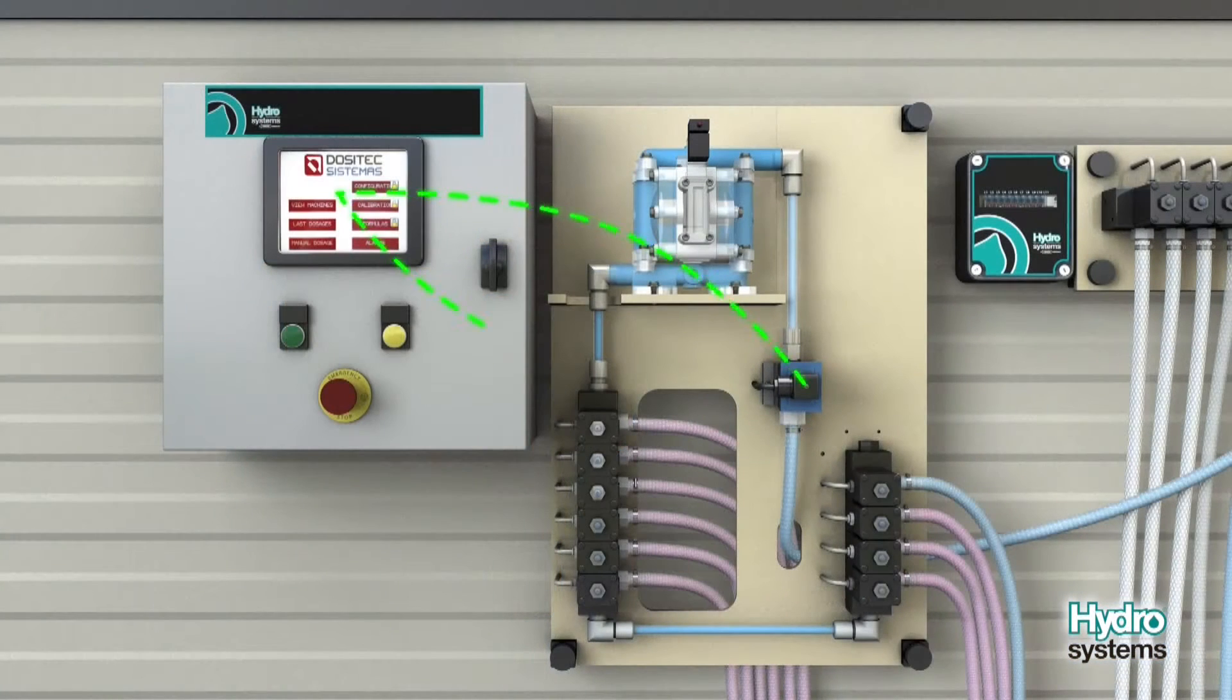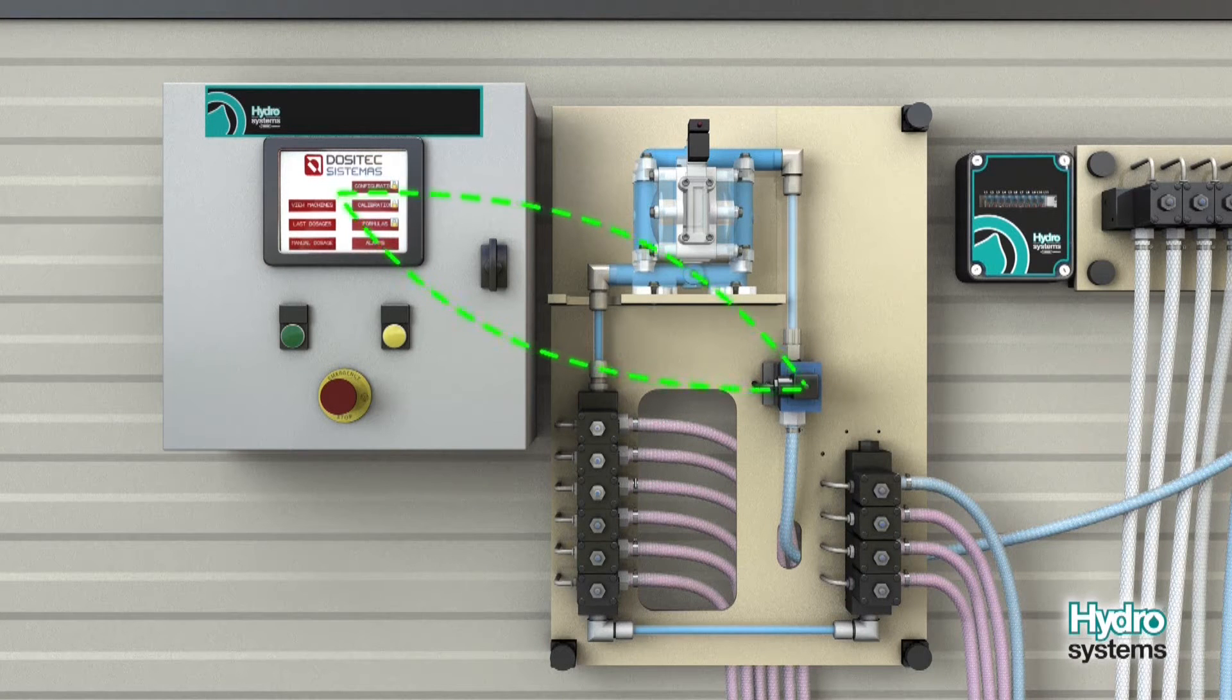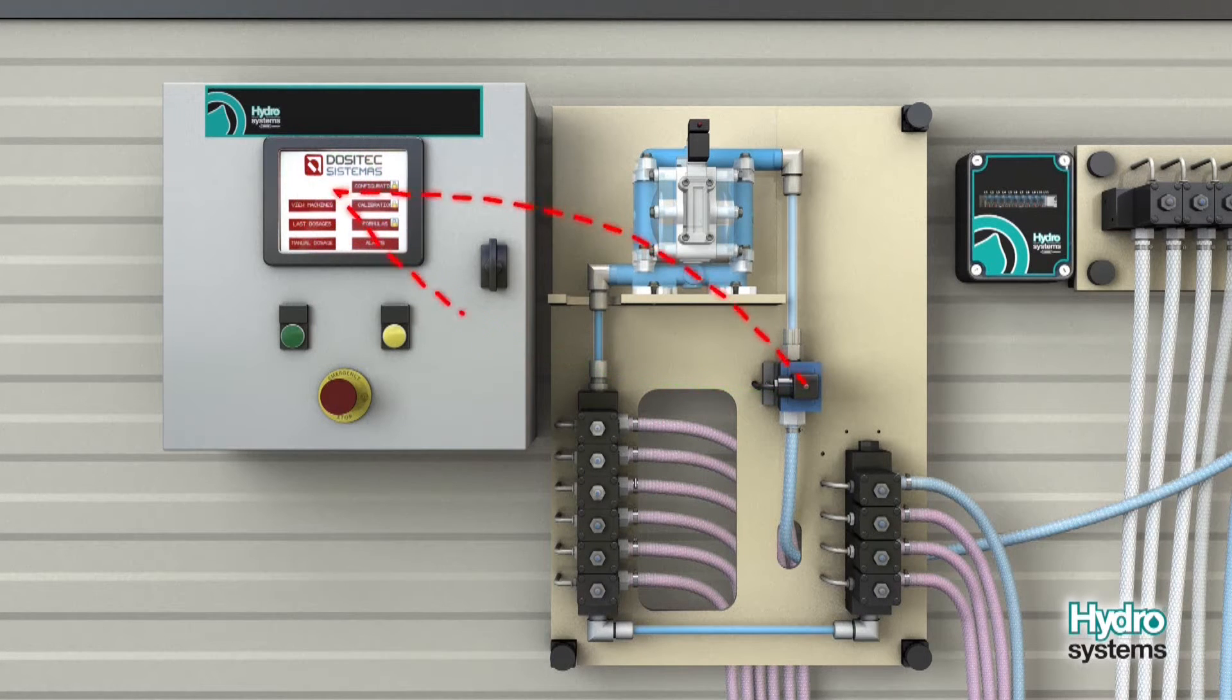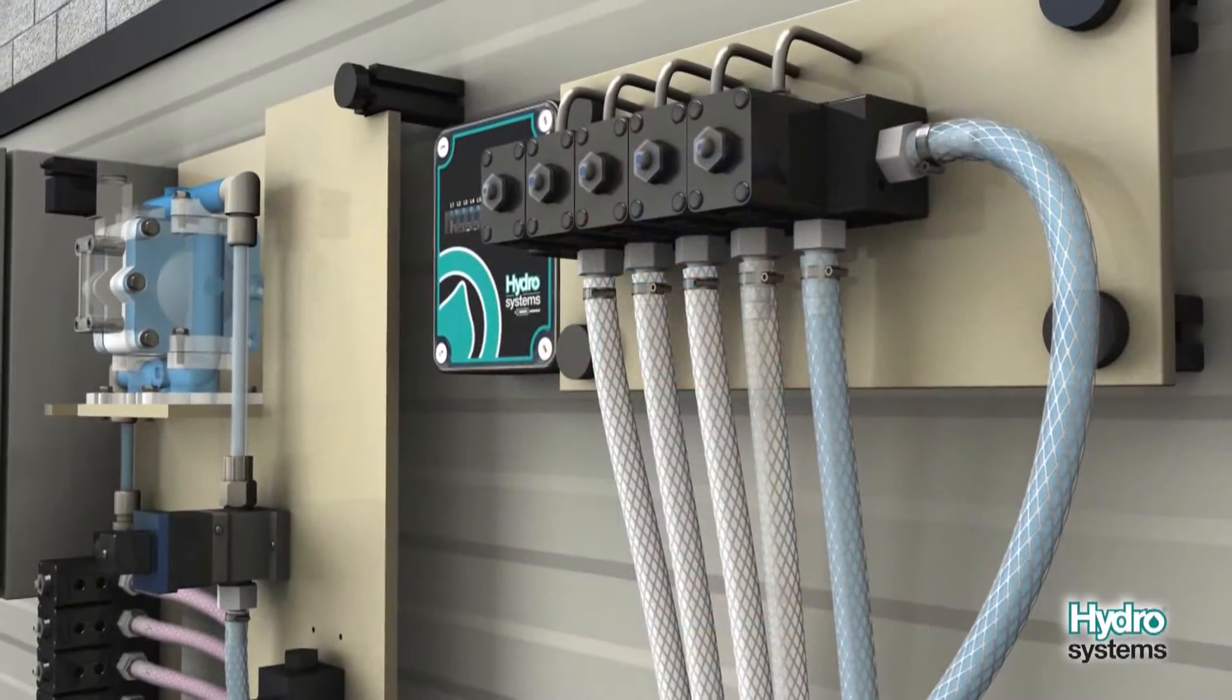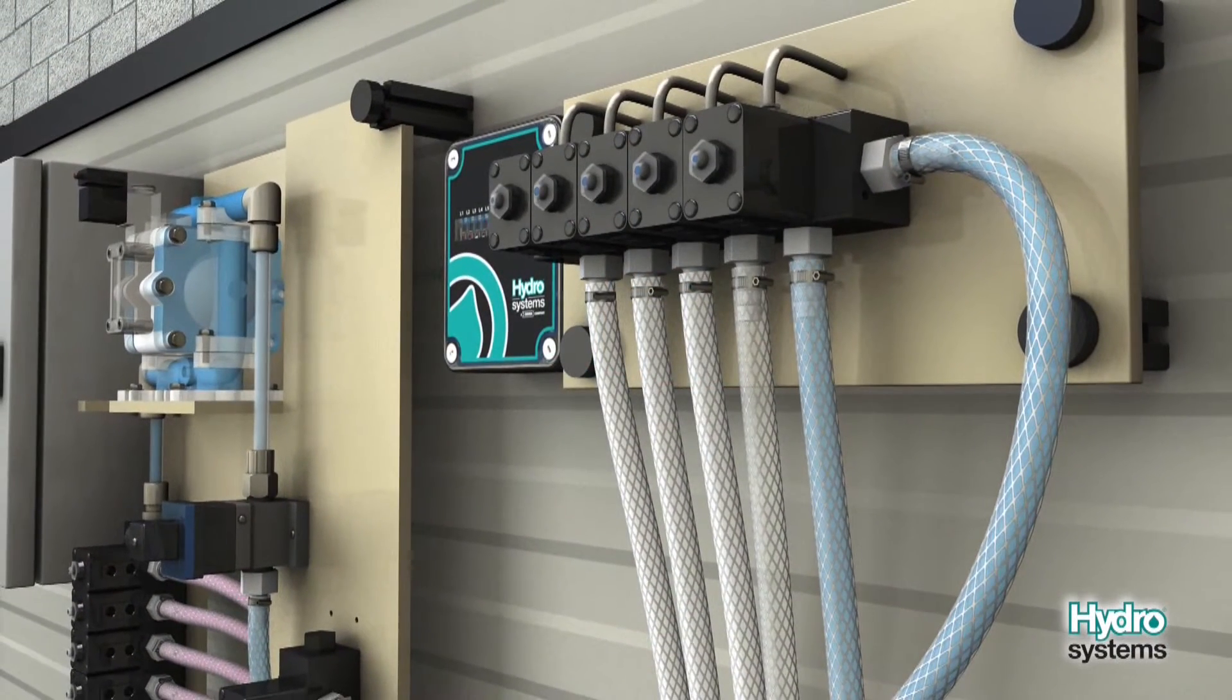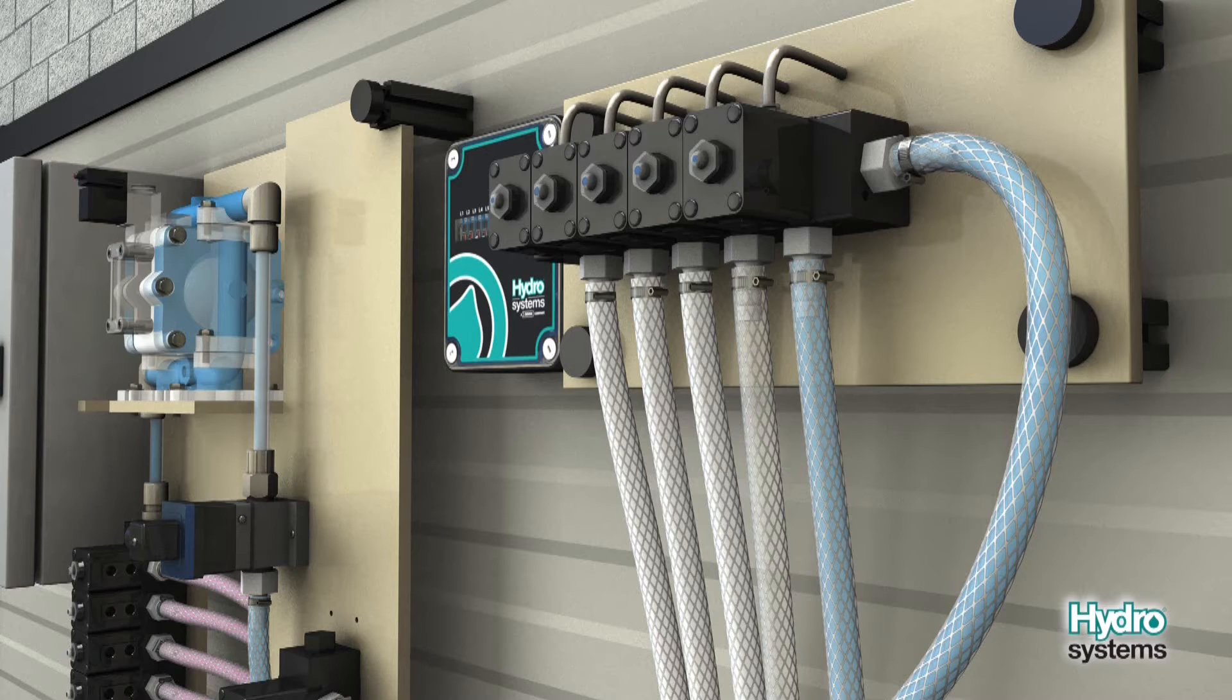If the PLC detects the correct number of pulses from the flow meter, the test is considered passed. If the correct number of pulses are not detected during the test, the test is failed and the dosage is aborted. An alarm is activated. After a successful test, the distributor valve to the washer is opened.